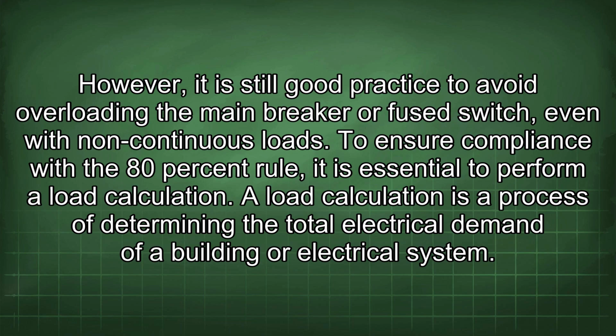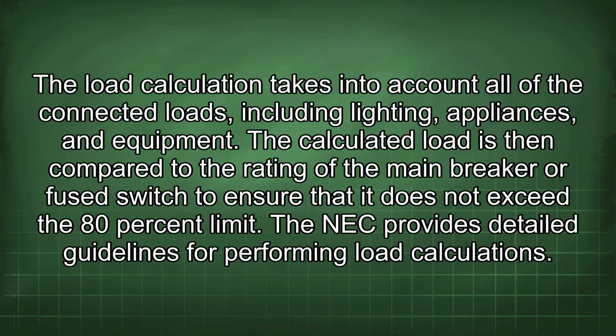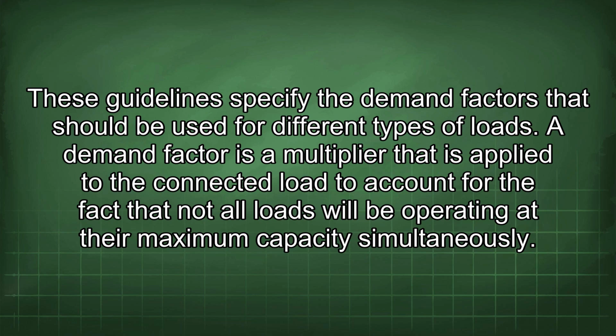To ensure compliance with the 80% rule, it is essential to perform a load calculation. A load calculation is a process of determining the total electrical demand of a building or electrical system. The load calculation takes into account all of the connected loads, including lighting, appliances, and equipment. The calculated load is then compared to the rating of the main breaker or fused switch to ensure that it does not exceed the 80% limit. The NEC provides detailed guidelines for performing load calculations. These guidelines specify the demand factors that should be used for different types of loads.